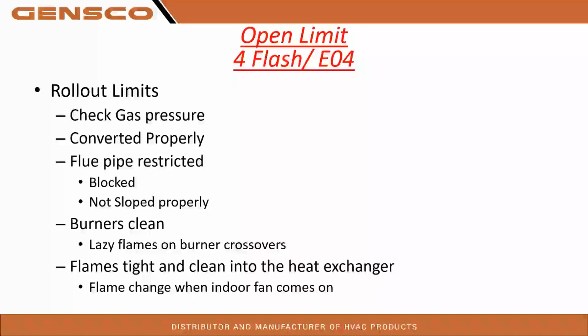If we can't get air out the flue pipe, we're getting the gas going the wrong way. We're getting that heat going the wrong way, right? So flue pipe restriction would be a big one. Maybe that bird's dead in the flue pipe somewhere, right? Causing some problems.